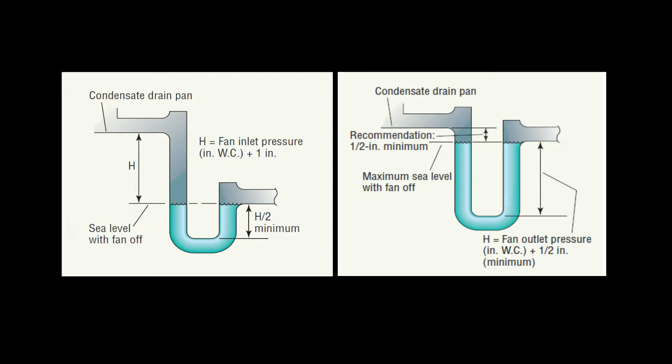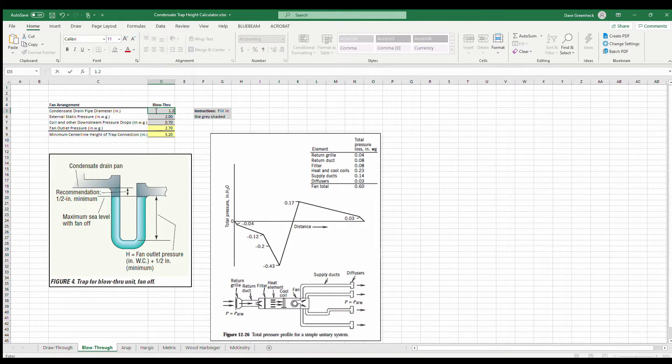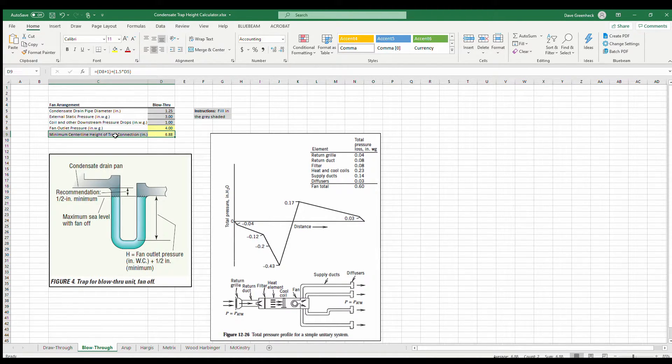So how do we size our condensate traps so that they work correctly and prevent these common problems from occurring? These graphics show traps for a draw-through and a blow-through arrangement with dimensions. The good news is Air Reps has created a calculation tool with equations for either draw-through or blow-through so you can get your answers quickly. All you need is condensate drain pipe diameter, external static pressure, coil pressure drop, and other downstream component pressure drops for a blow-through arrangement. And if you aren't sure what draw-through or blow-through is, we have graphics that illustrate the difference.